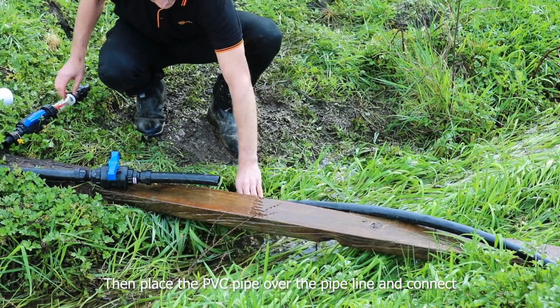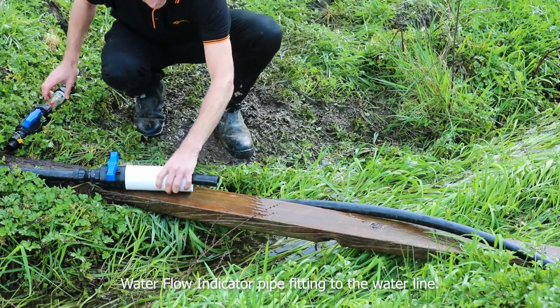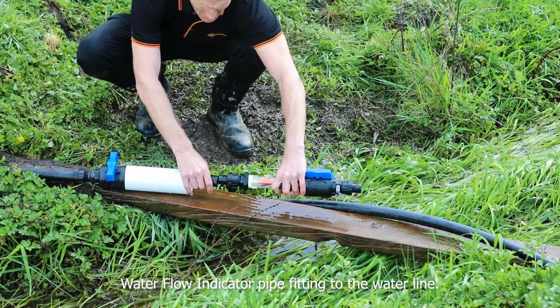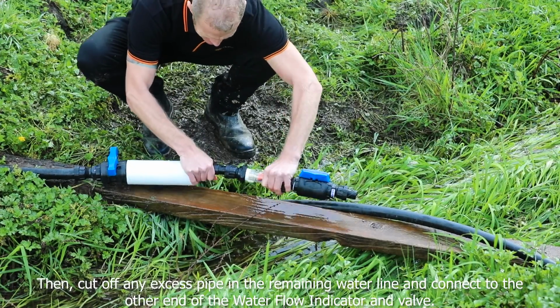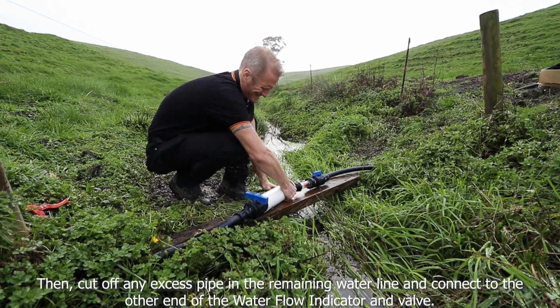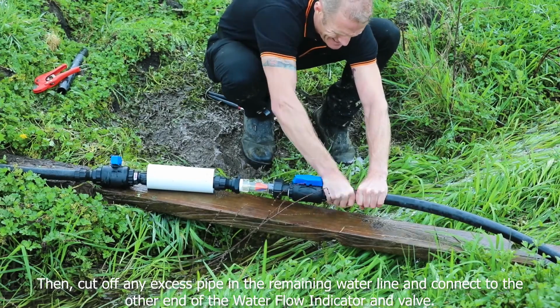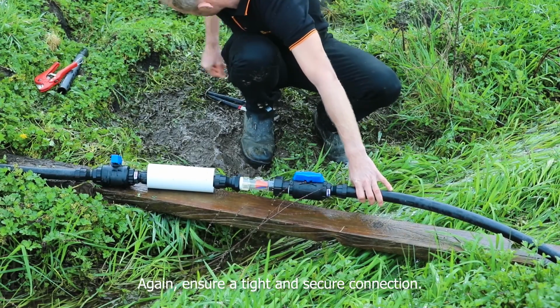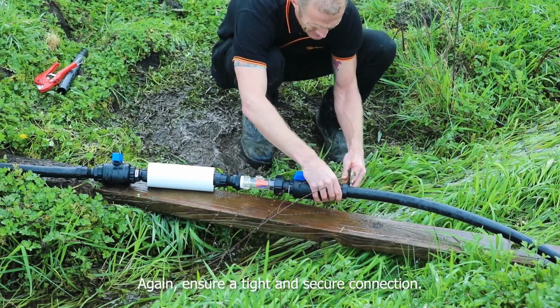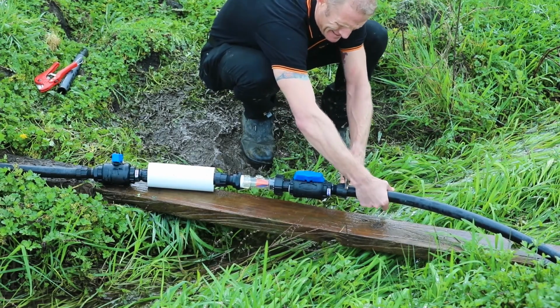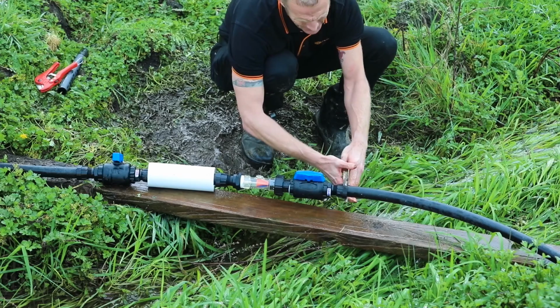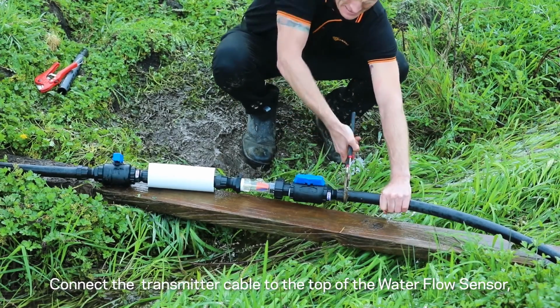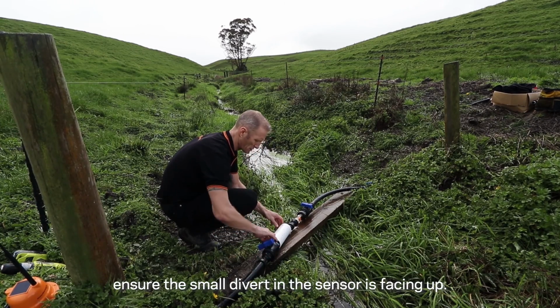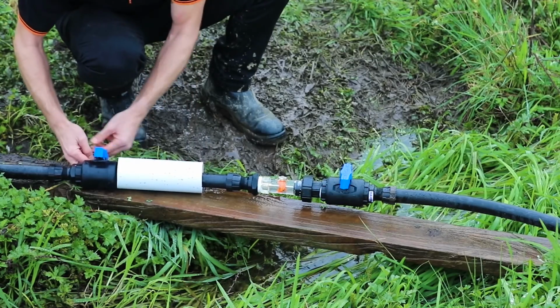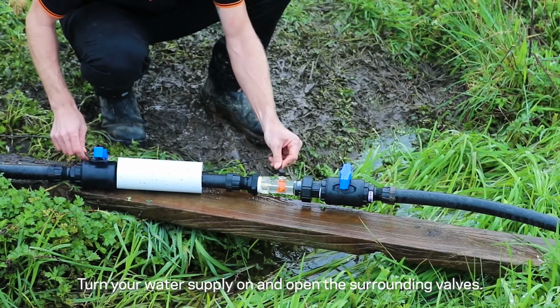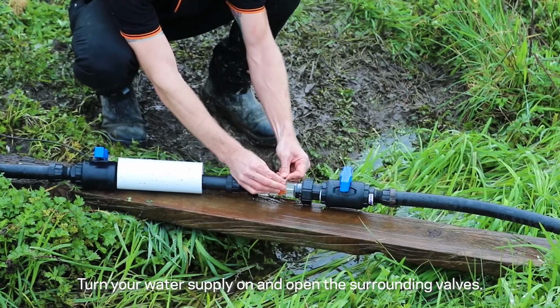Then place the PVC pipe over the pipeline and connect the water flow sensor pipe fitting to the water line. Then cut off any excess pipe in the remaining water line and connect to the other end of the water flow sensor and valve. Again, ensure a tight and secure connection. Connect the transmitter cable to the top of the water flow sensor. Ensure the small divot in the sensor is facing up. Turn your water supply on and open the surrounding valves.